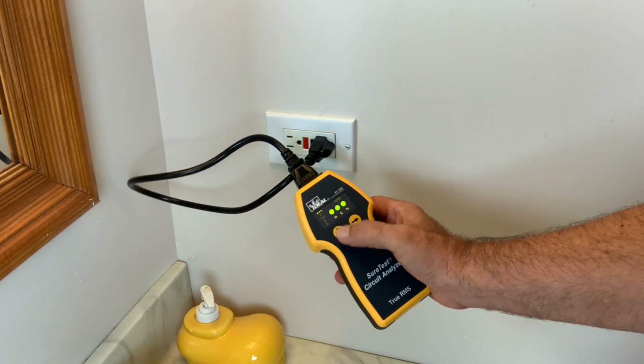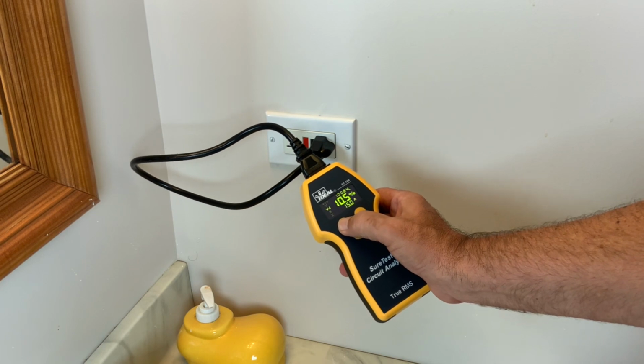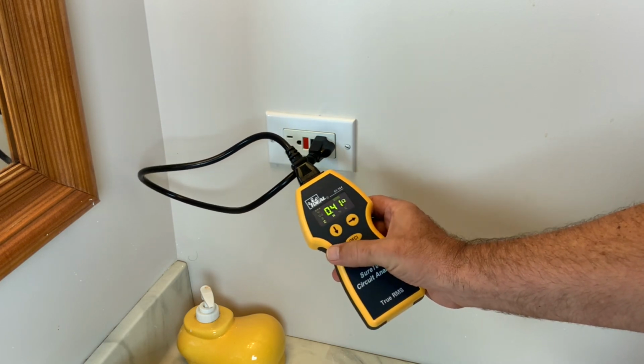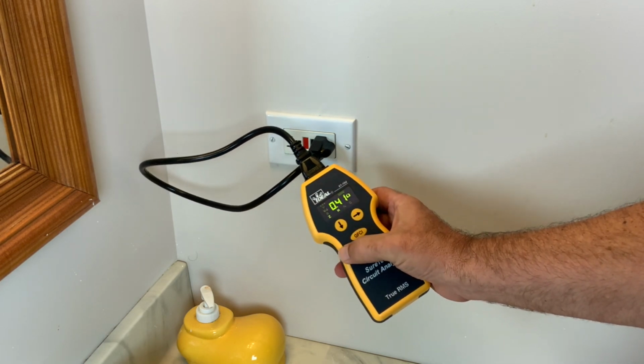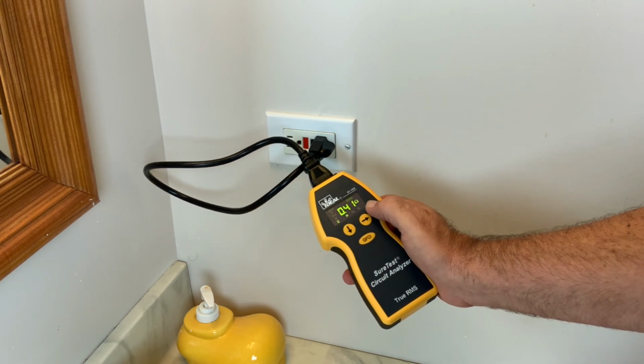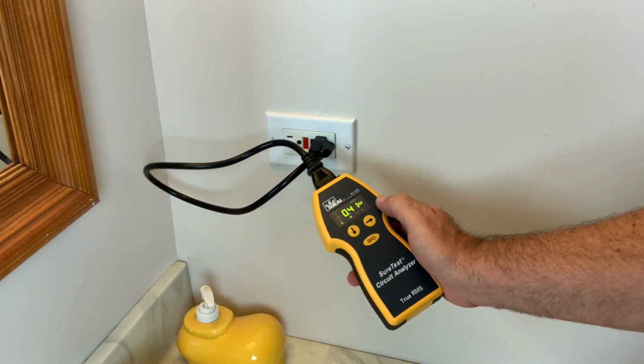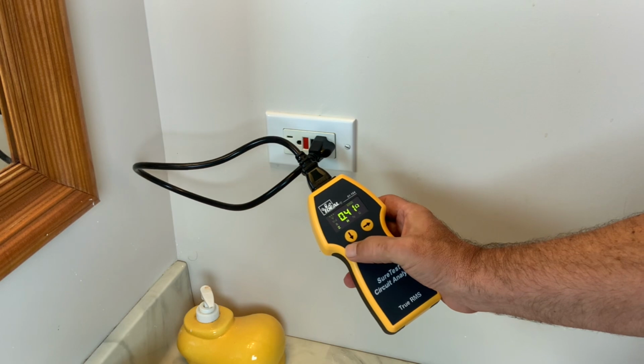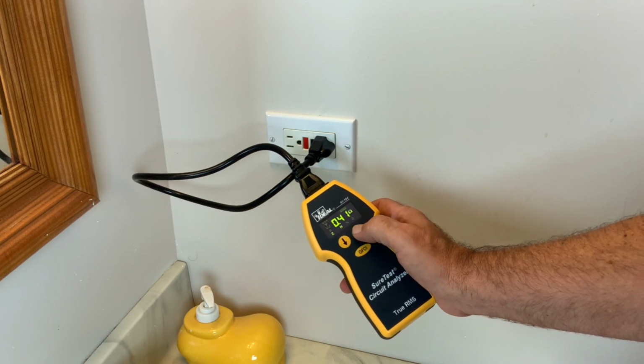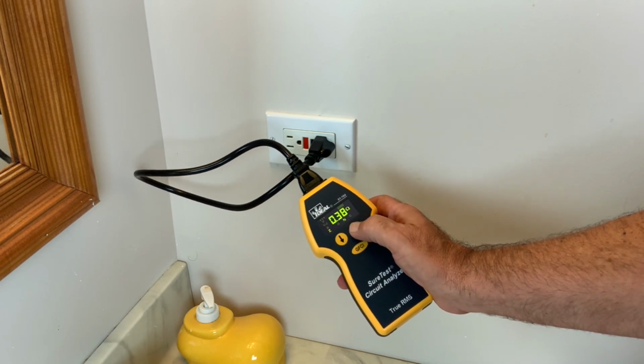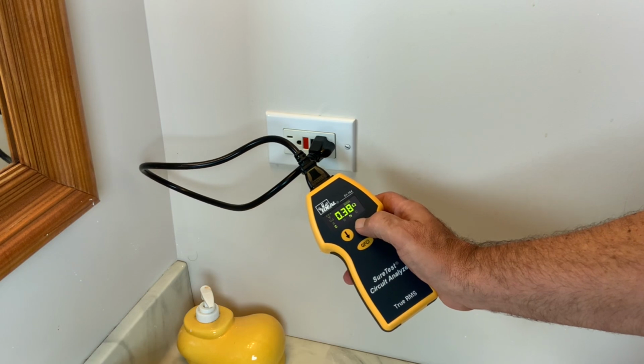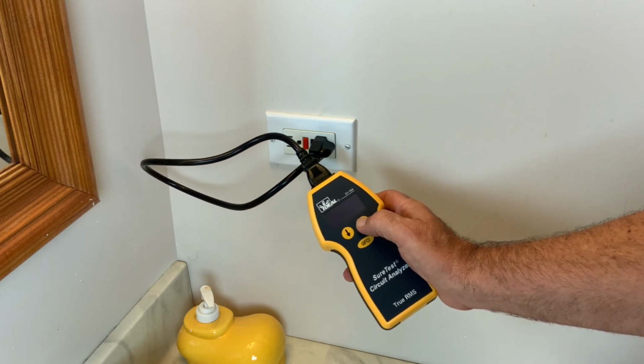One last thing to note about GFCI outlets is that when you're testing impedance, you can't test your ground impedance on a GFCI because that will cause the outlet to trip. So I'm looking at my hot impedance right now, my neutral, and as soon as I switch to the ground impedance, I'm going to trip that breaker.